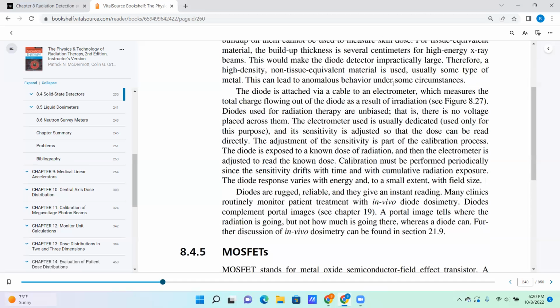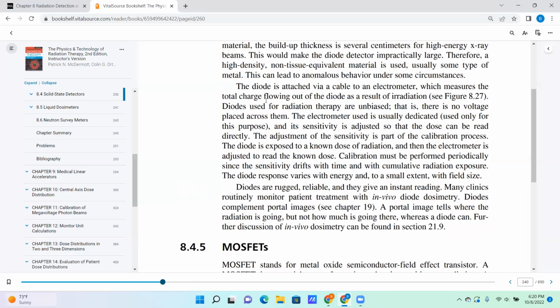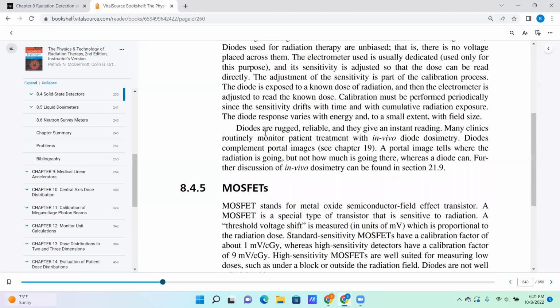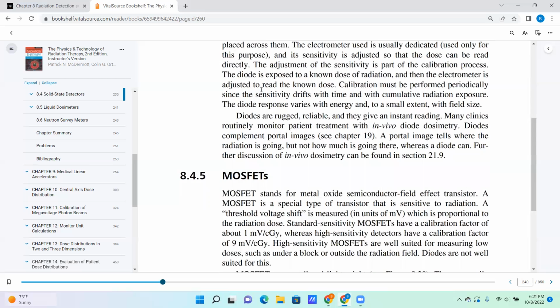So the diode is attached by a cable to an electrometer, which measures the total charge flowing out of the diode. Diodes used for radiation therapy are unbiased. In other words, there's no voltage placed across them. The electrometer is usually dedicated, and its sensitivity is adjusted so that the dose can be read directly. The adjustment of the sensitivity is part of the calibration process. The diode is exposed to a known dose of radiation, then the electrometer is adjusted to read the known dose. Calibration must be performed periodically since the sensitivity drifts with time and with cumulative radiation exposure.